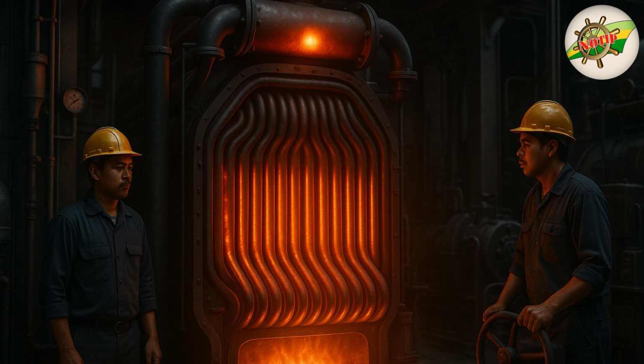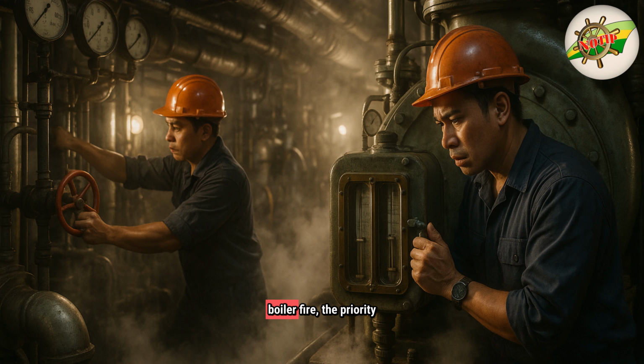In a water tube boiler, the risk is more severe due to its high-pressure steam system. A fire may originate from the furnace or from rapidly rising temperatures caused by flame impingement or fuel malfunctions. Overheating of tubes can lead to evaporation of water, tube deformation, rupture, or even explosion if cooling is not restored. To control a water tube boiler fire, the priority is to stabilize water levels and cut off fuel safely. Cooling the furnace must be done gradually, never by spraying water directly on the hot surfaces. Engineers must follow the manufacturer's emergency shutdown procedures and monitor boiler pressure continuously. Preventive maintenance, routine burn tests, and strict fuel management significantly reduce this hazard.